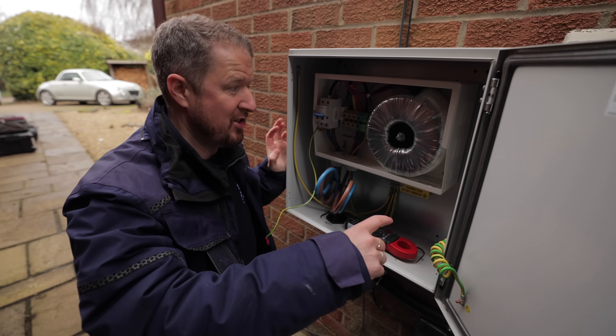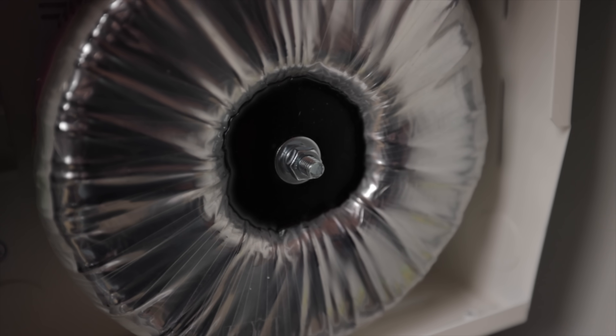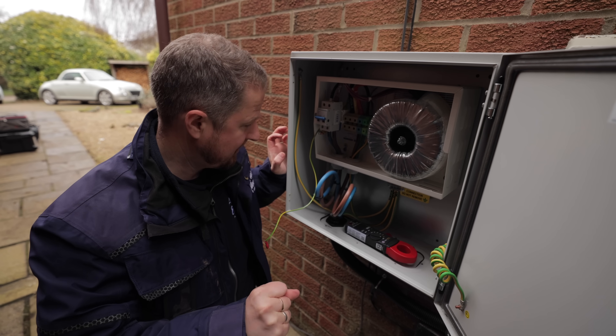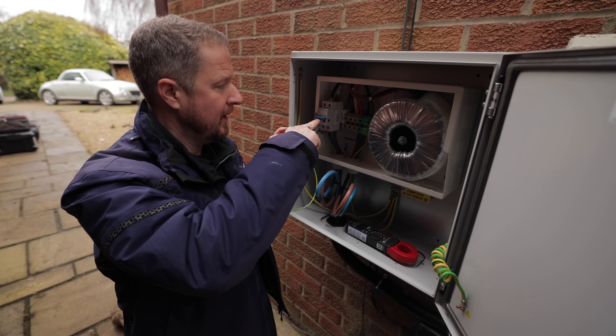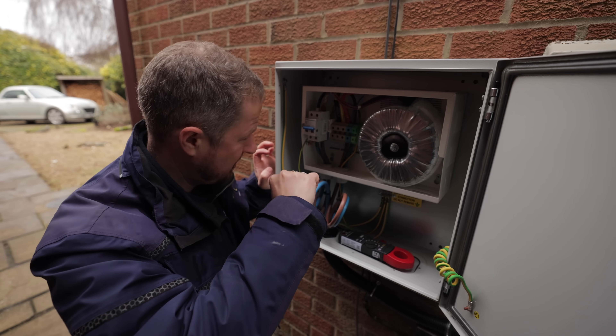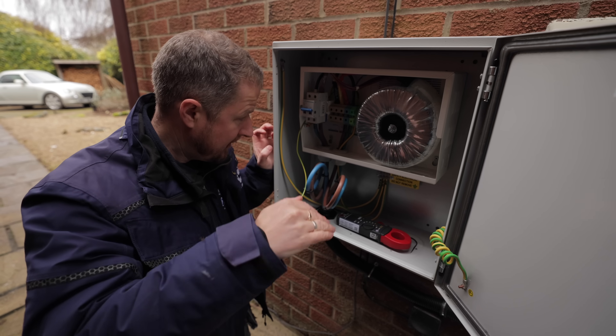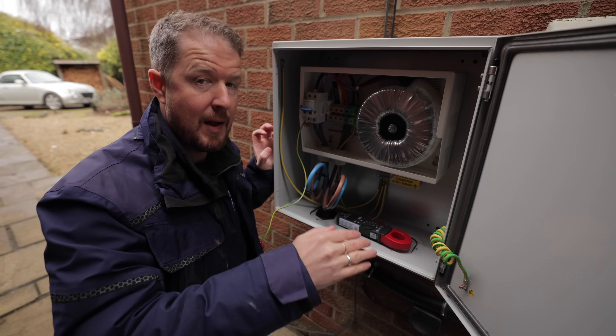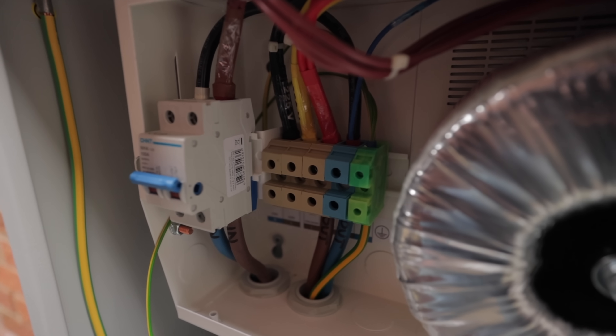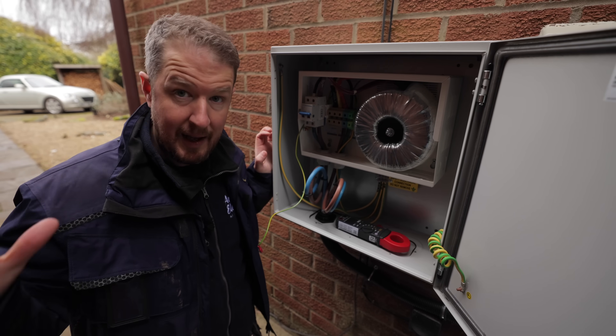This is effectively a giant transformer. This big lump here is a copper winding and we run the entire power for the whole house through this transformer — it steps the voltage down by a certain percentage. We've got our incoming tails from the meter coming into a main switch, then through this winding. It's tapped off in three different places: the first option — 'low saving' — drops the voltage by about 6%; the second — 'medium saving' — drops it by 8%; and the third drops it by about 10%. We decided to start small and drop things by about 6%, coming out of that first tapping.